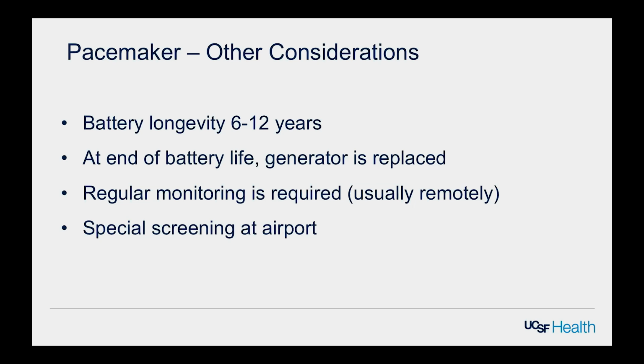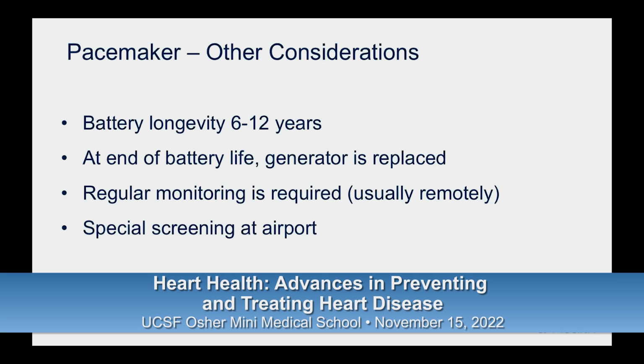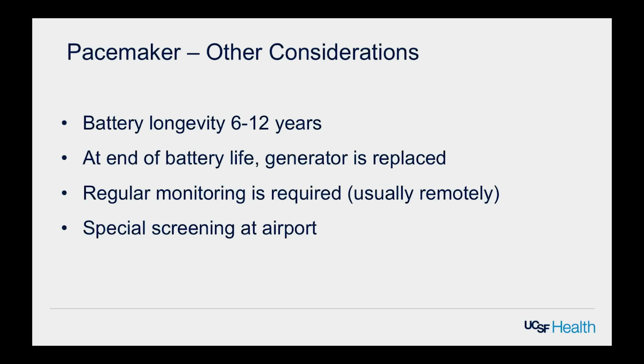Patients always ask about this. What happens when they go to the airport? So for most patients with pacemakers, they'll undergo special screening at the airport. But to be honest, we in electrophysiology are not that worried about the patient setting off the metal detector. That may be what the patient's worried about. But actually what we're concerned about is that the surveillance or screening equipment emits electromagnetic interference. And what we're concerned about is that the pacemaker can sense that electromagnetic interference and mistake it for a heart rhythm. And if the pacemaker stops pacing in a patient who is dependent upon that pacing because it's seeing this electrical noise, the patient could then pass out. Or if they have a defibrillator, they could get shocked by their defibrillator. That's really what we're concerned about.